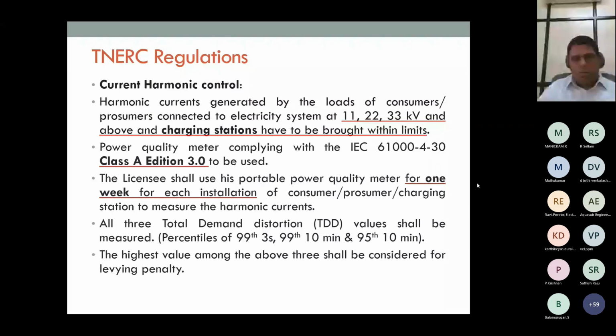Every HT consumer will be measured for one whole week. It is not that somebody measures for 2 hours, 3 hours and says you are not complying. So it will be a whole week of measurement. For example, with one meter, every year there are only 52 weeks, so probably 46, 47 consumers only they will be able to cover. So they may need about 250 meters to cover all the 10,600 HT consumers in our state. That is a large volume, and I do not know what they have done.